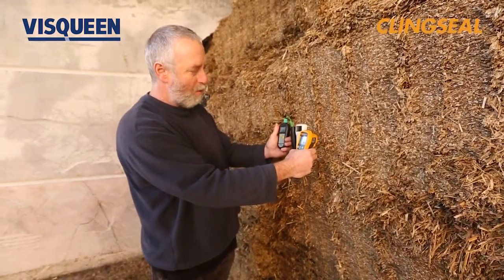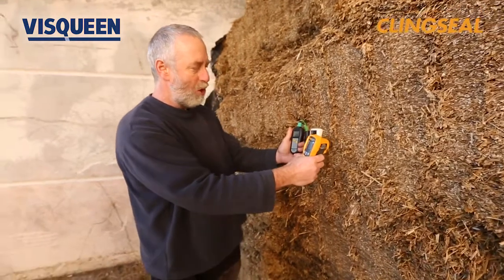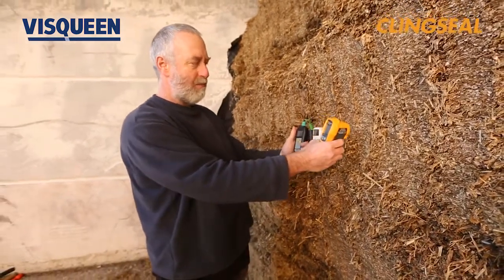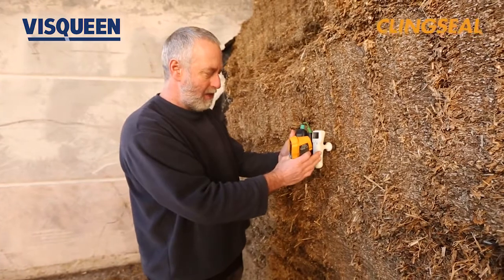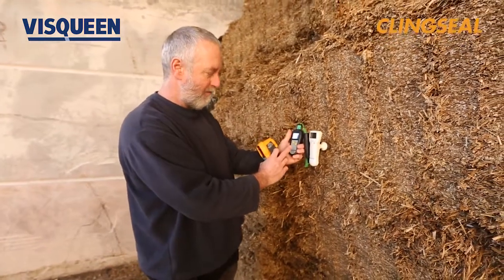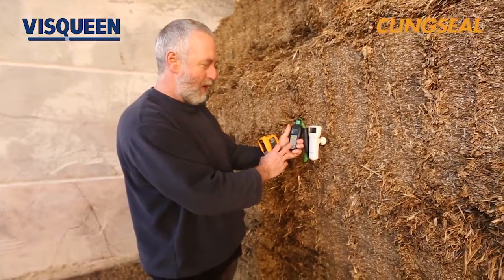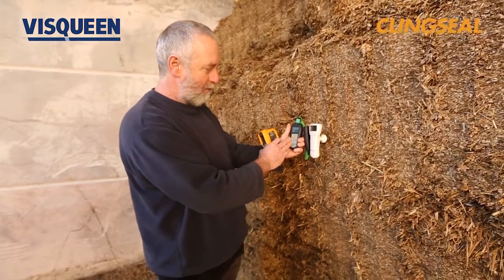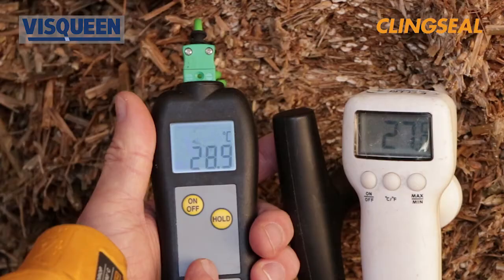It's much more important to actually look at the relative temperature between the 12 centimeter and the 50 centimeter probe. On this clamp we can see that the deep probe is 28.9 and the short probe is 27.